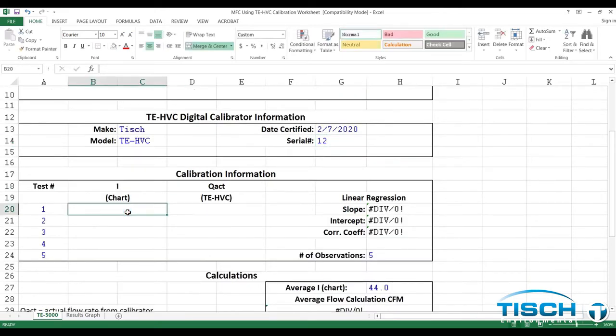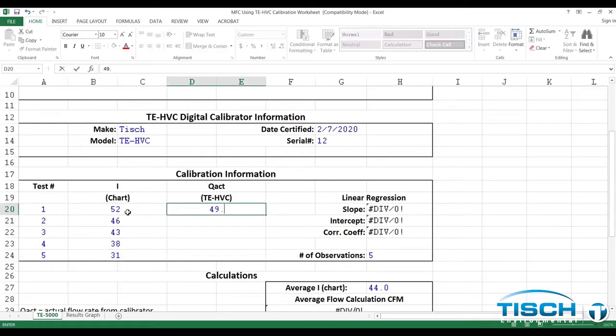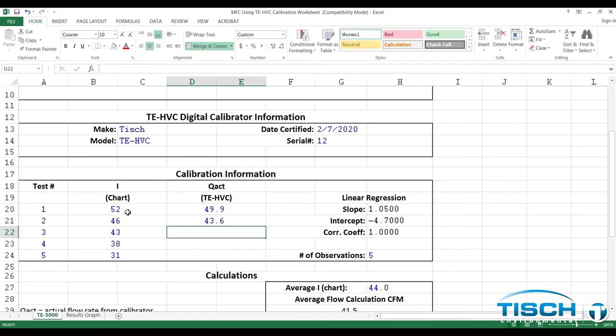First, enter the chart readings. In our example, they are 52, 46, 43, 38, and 31. Then you will need to enter the Q ambient readings from the calibrator. Ours were 49.9, 43.6, 40.5, 34.6, and 28.8.